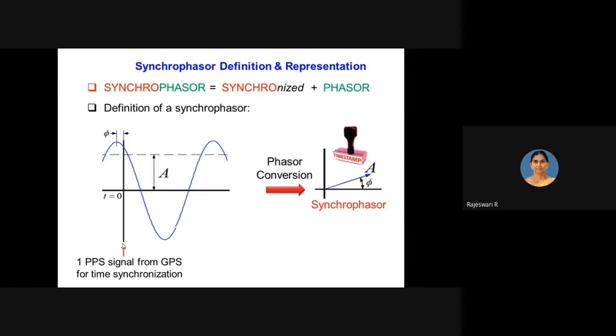What is this time reference axis? It is actually received from GPS, which initiates the time synchronization used for getting this property. One pulse per second signal is received from the GPS satellite system for time synchronization. So once it's received, if the PMU, the box which is measuring this phasor, receives one pulse per second from the GPS system, that signal is considered as a reference. With respect to this reference, the phase angle is measured.